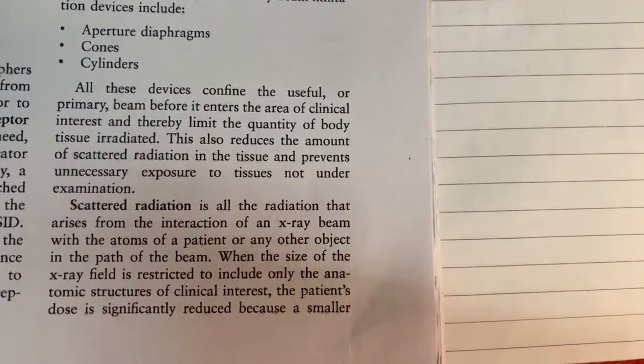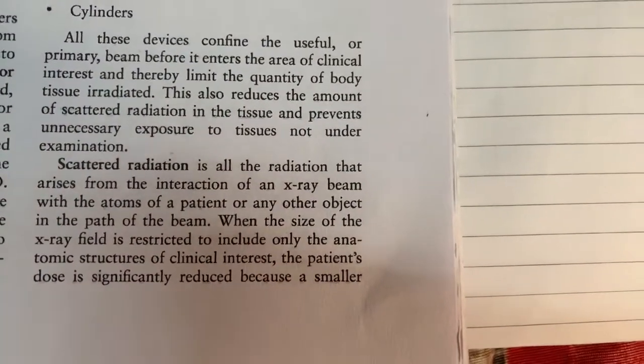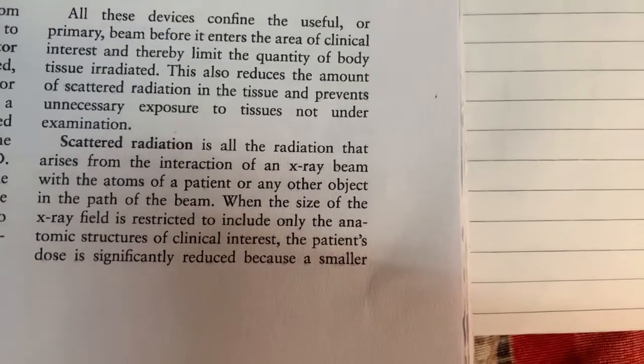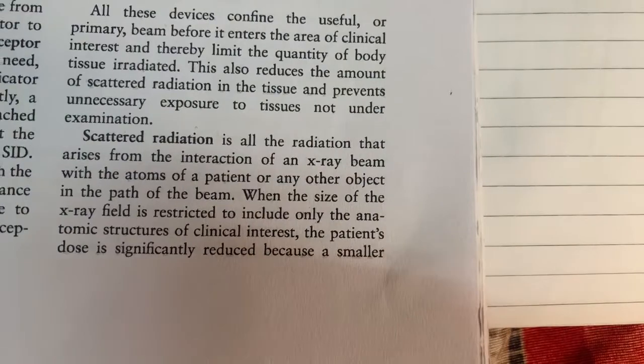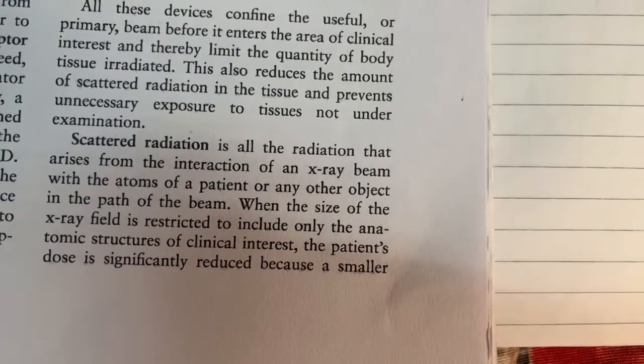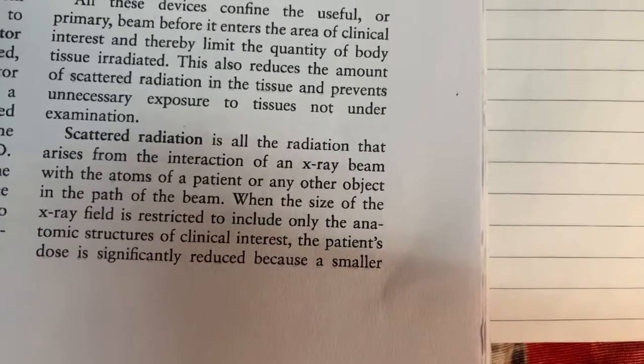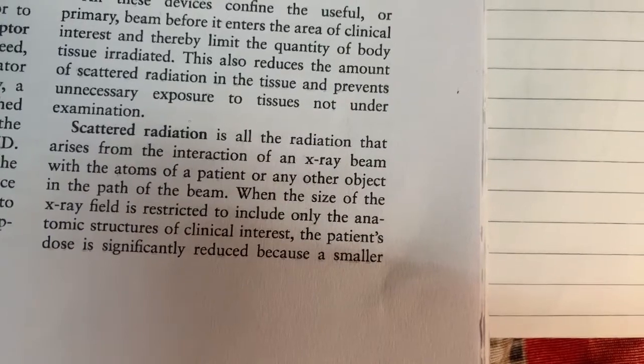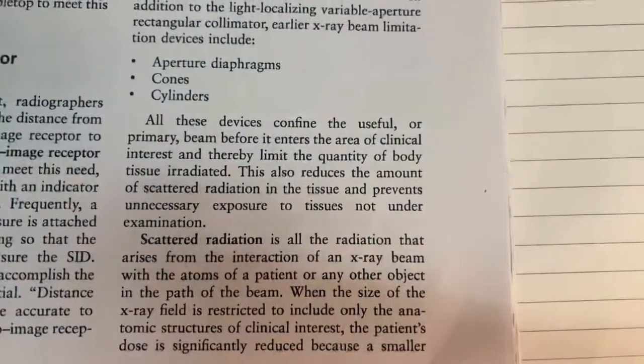These devices also reduce the amount of scattered radiation in the tissue and prevent unnecessary exposure to tissues not under examination. Scattered radiation is all radiation that arises from the interaction of an X-ray beam with the atoms of a patient or any other object in the path of the beam. When the X-ray field is restricted to only the anatomic structures of clinical interest, patient dose is significantly reduced.